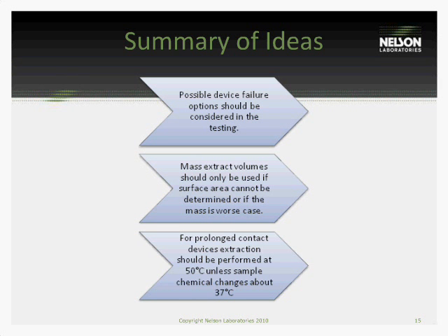The next one is sample preparation. For biocompatibility, we've always looked at two ratios of how to get the device into a solution, how to extract it. Those have been based either on the surface area of the device, so the larger the surface area, the more volume we add, or by weight. The heavier it is, the more volume we add. It's been kind of ambiguous in the standard on which one to use. Recently the FDA has been very strong on using the surface area, and once again they mention here that surface area should be used. After this slide I'll show you an example why that is, but just keep that in your mind for right now.